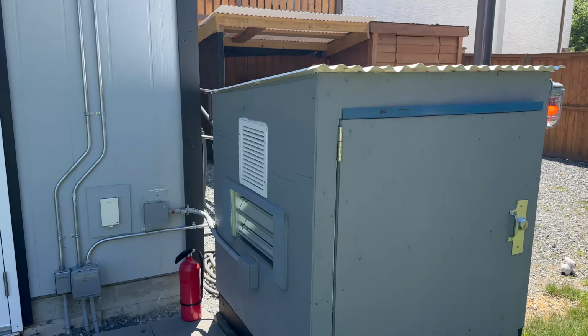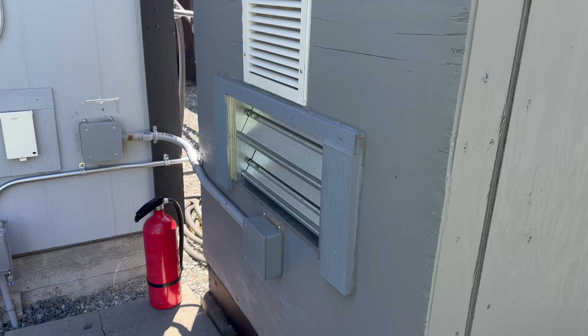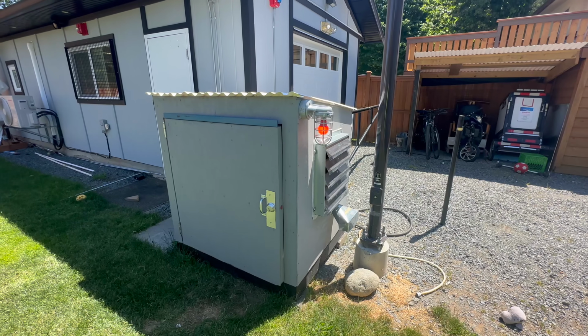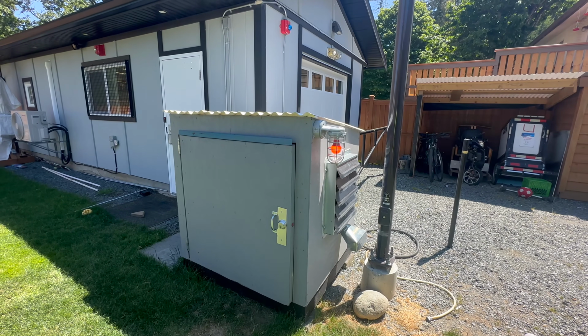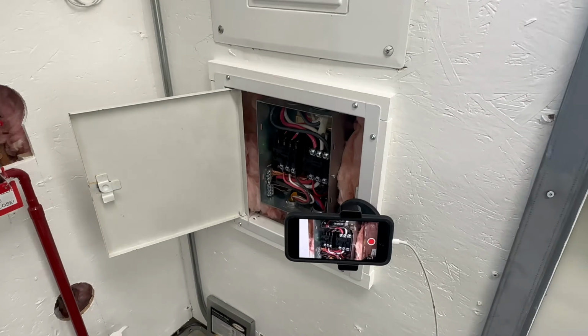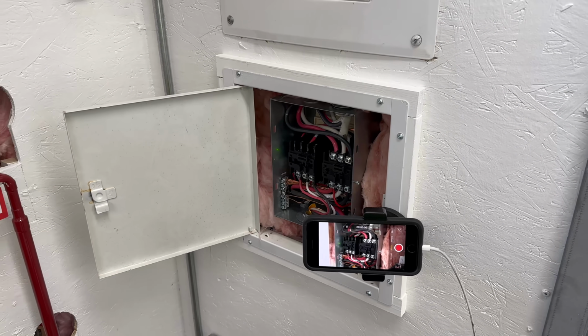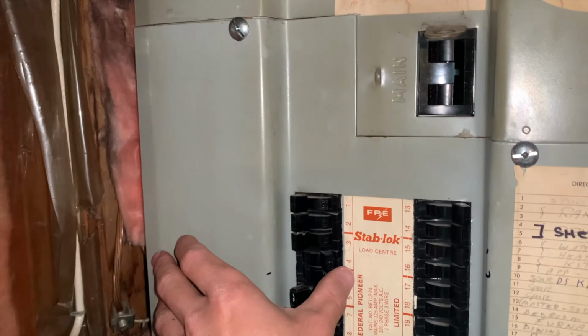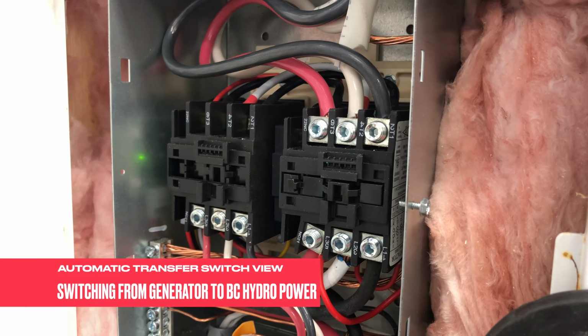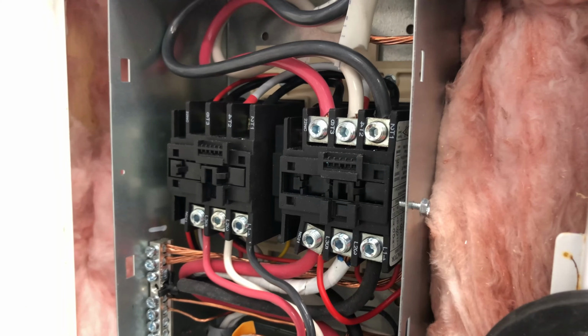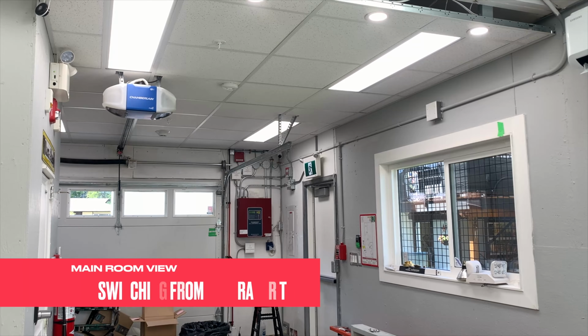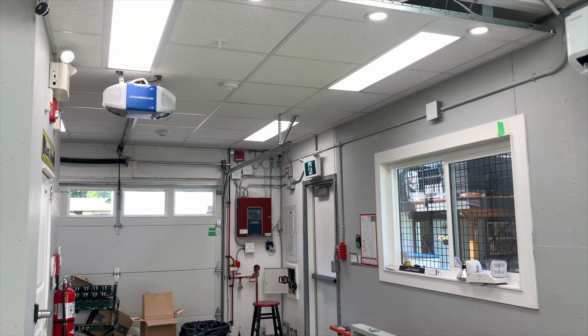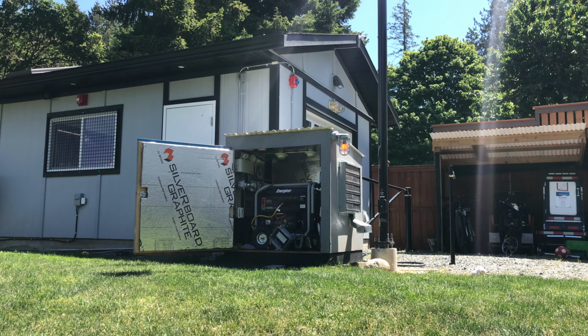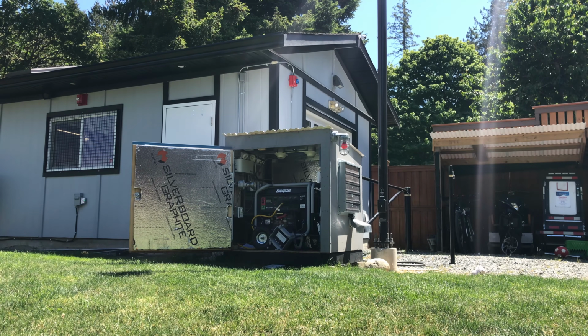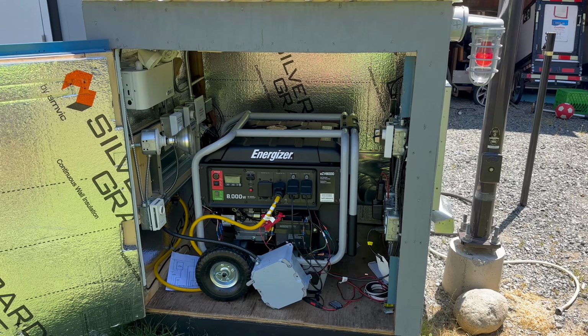And you can see that the cooling system has just come on. It has now opened up those dampers at this end, as well as the fan is running on this end here. I will now shut the generator back down by restoring power to the building, and you will see how quickly the power will transfer back over. I will run all the same camera angles of the switch back over to BC Hydro power. Okay, I will restore power now. That concludes my video on the automatic generator setup.